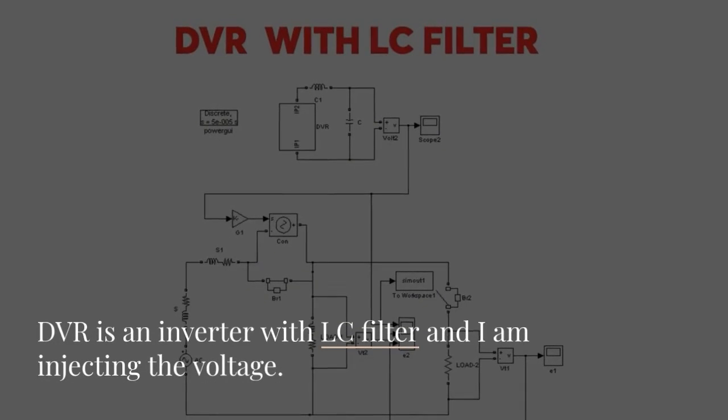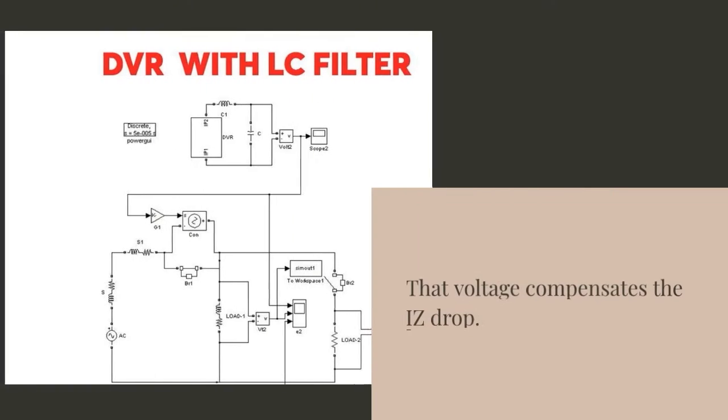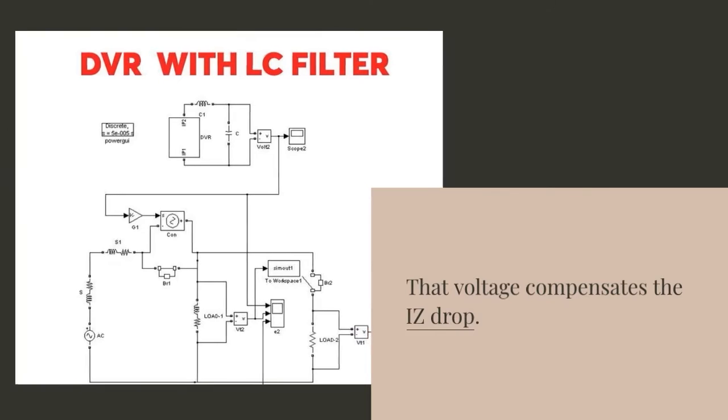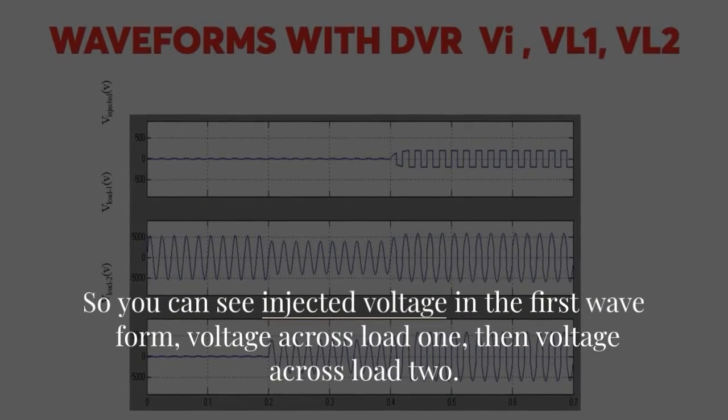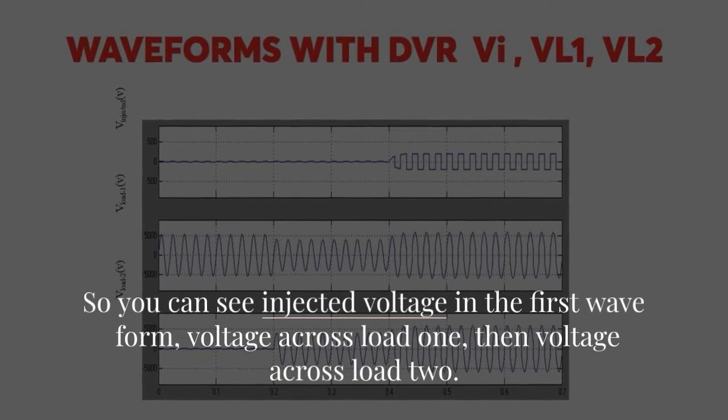Then with DVR I am injecting the voltage. DVR is an inverter with LC filter and I am injecting the voltage. That voltage compensates the IZ drop. So you can see injected voltage in the first waveform, voltage across load 1 then voltage across load 2.